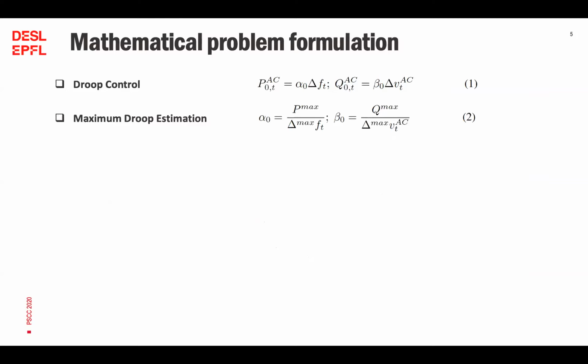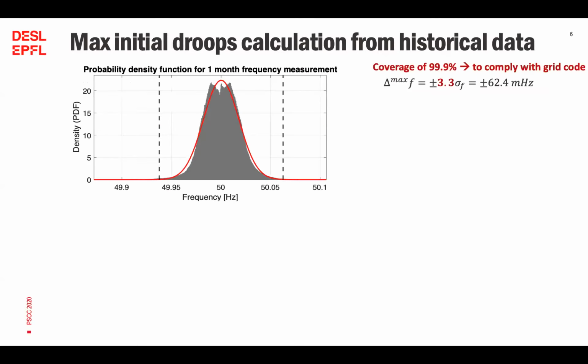Of course, the provision of the service is maximized by the maximization of the droop constants, alpha and beta, for given maximum values of P and Q that are given by the installation itself. And that will be set for the maximum deviation of the input variables.